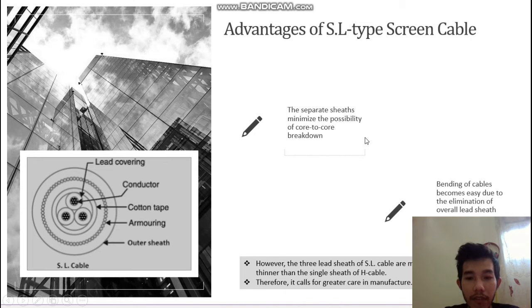However, the three lead sheaths of SL cable are thinner than the H-type. So even though the SL type has three conductors, its sheaths are thinner than the single sheath of H cables. Therefore, it calls for greater care of manufacture. The construction of the SL type cable depends on the ability of the cables and the usage of the cable, because the cable is up to 66 kilovolts. So that's why the construction has the lead covering, cotton tape, armoring, and outer sheath. This is the suitable construction for each situation. Okay, that's all for the SL type screen cables.